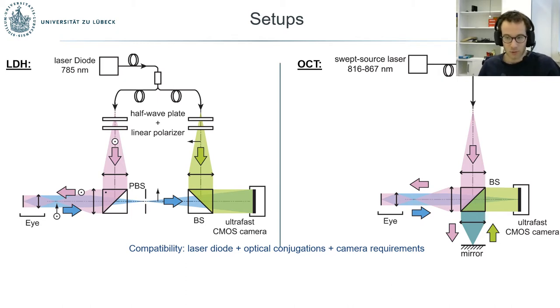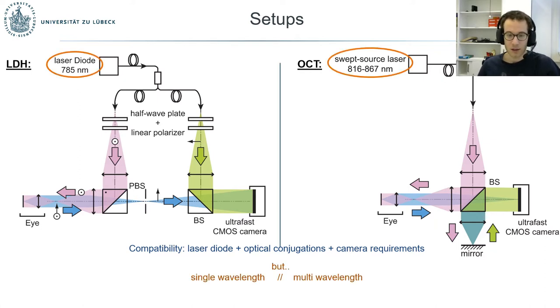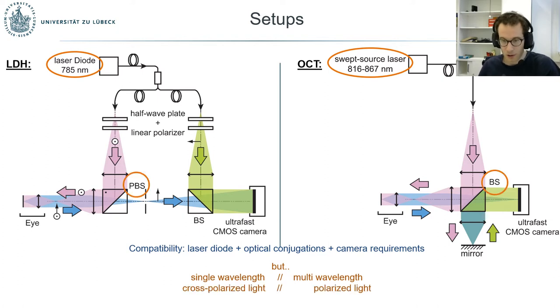For LDH, the 60 kHz frame rate is about sampling Doppler frequency shifts up to a few tens of kHz. With OCT, it's about freezing the motion of the eye during the measurement of a volume, also requiring about 60 kHz. The key difference is that LDH uses a single wavelength to detect Doppler fluctuations, whereas OCT requires multiple wavelengths.